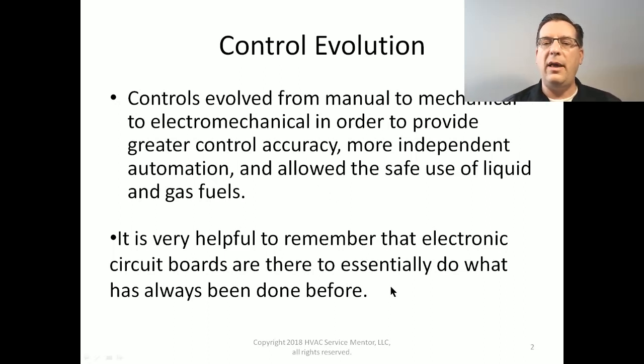It's really helpful for us to remember that electronic circuit boards are there to essentially do what has always been done before. Imagine our gas furnace, for example. What is it supposed to do? It's supposed to turn a burner flame on at the right temperature, turn it off at the right temperature. It's supposed to turn a fan on at the right time and turn it off at the right time. And that all used to be done by mechanical and electromechanical controls. And now it's done by electronic controls. It's doing the same thing, only more independently, more automatically, more accurately, and also more safely. I want to illustrate that real quick here. Let me get my pointer in the right place. There we are. Check this out.